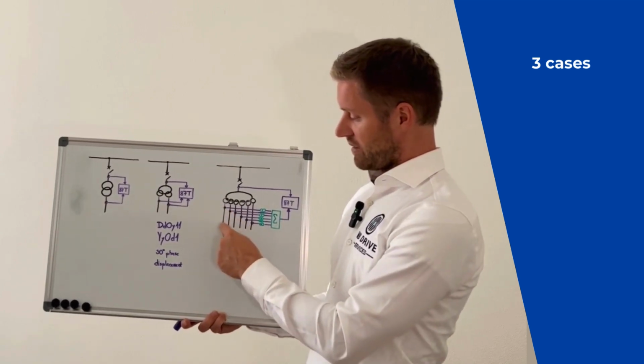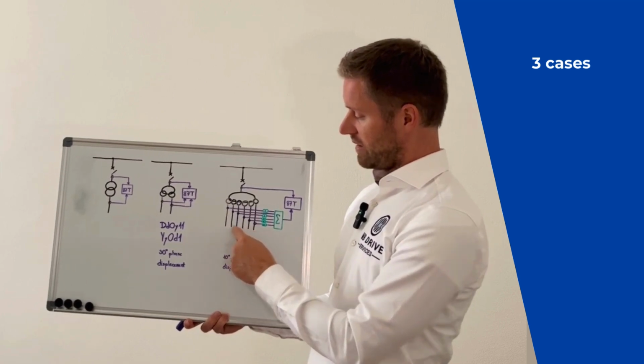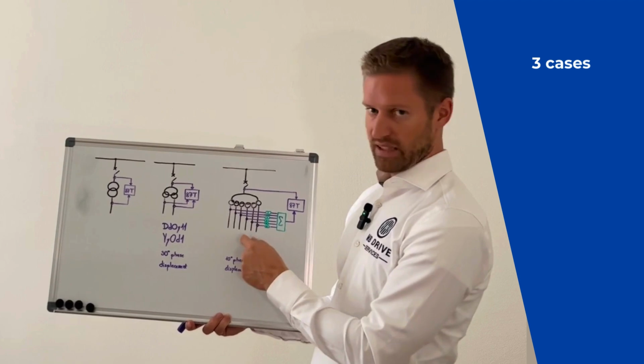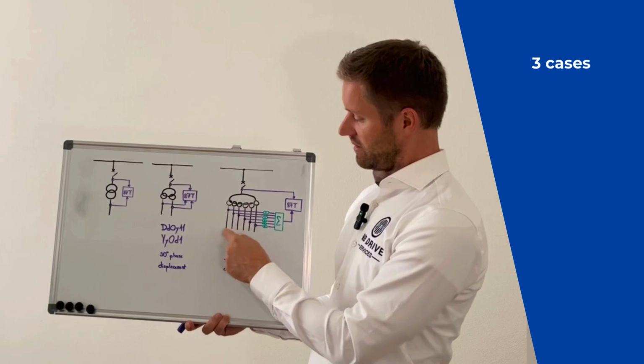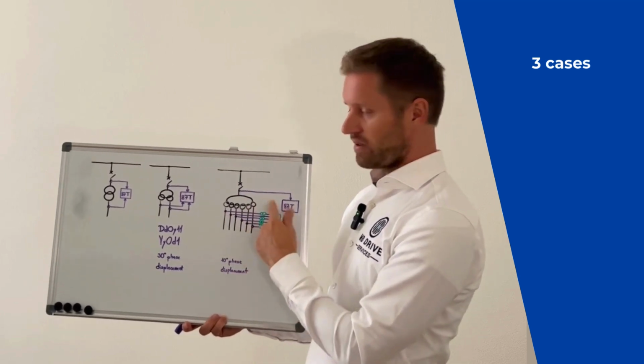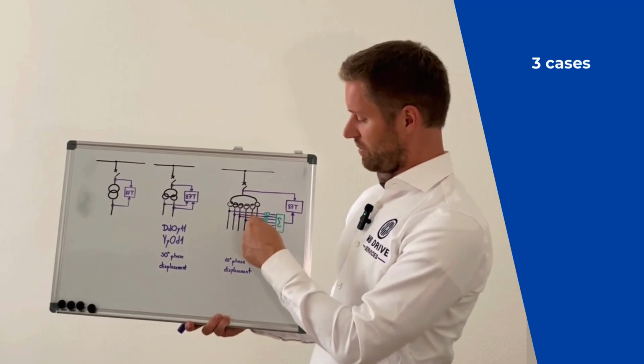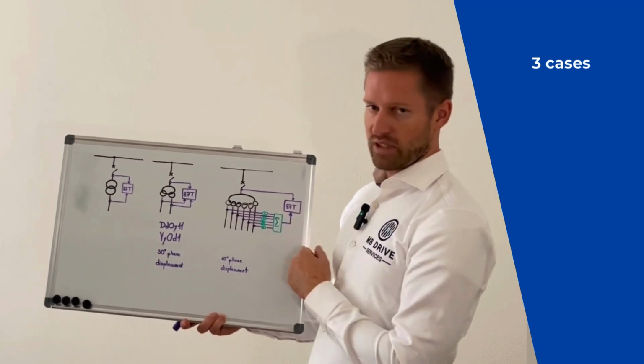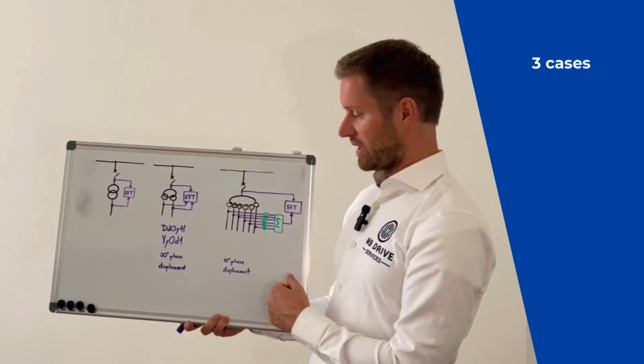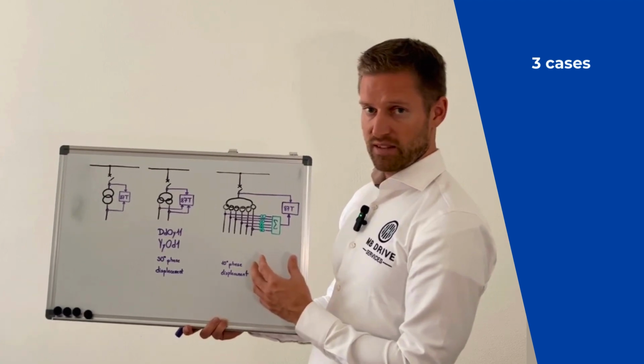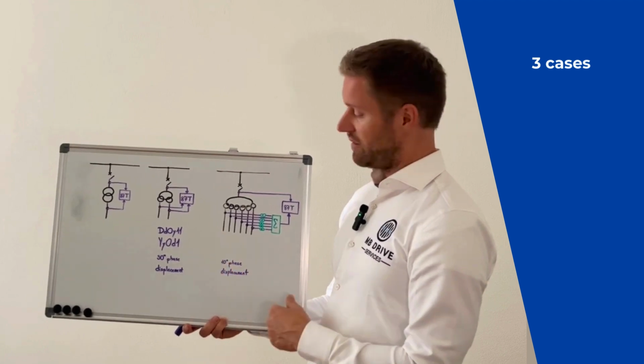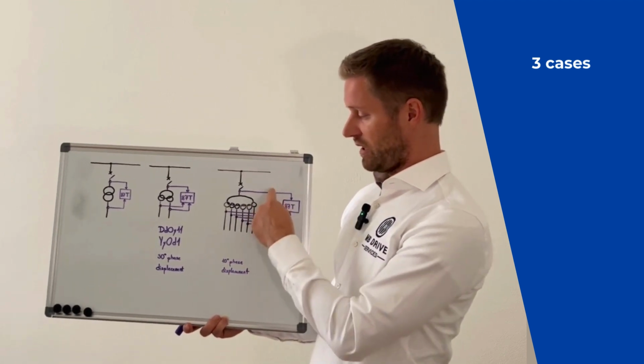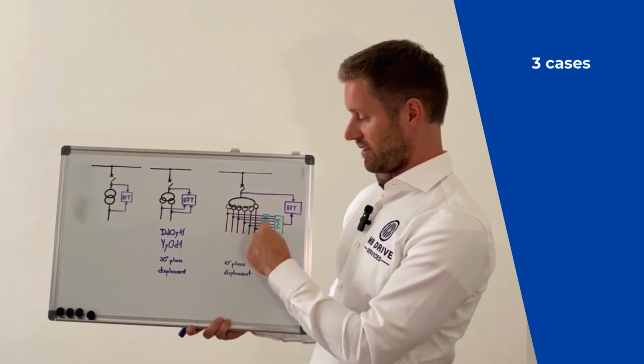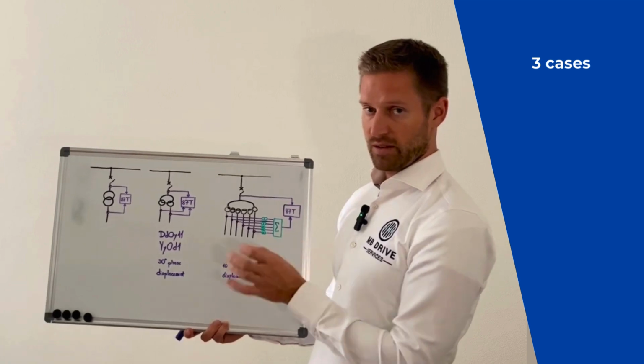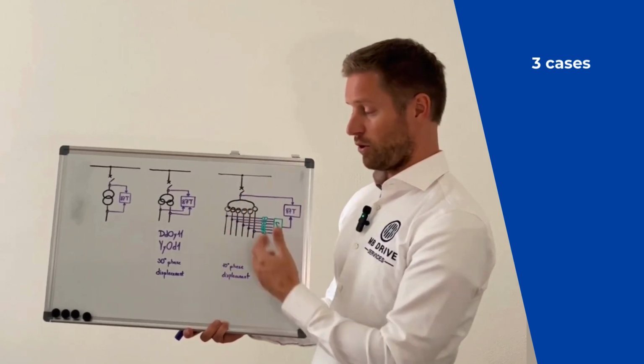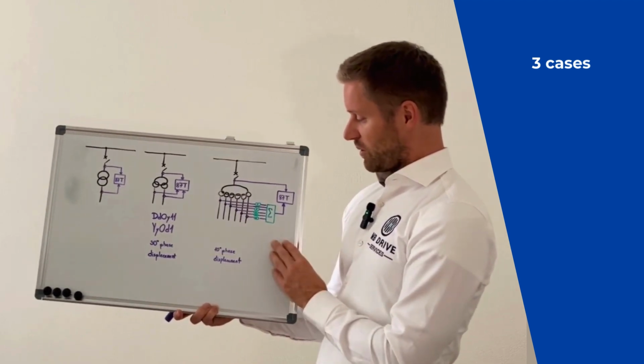And then as the windings are phase displaced, the currents flowing in each secondary winding are not in phase with each other, so we cannot just sum them up arithmetically. If you would just sum them up and feed the sum into the relay, then it would trip immediately. Because as I explained earlier, differential protection is appreciated mainly because of its sensitivity, and here we would have an error. The primary current would not be the same as this arithmetic sum of the secondary currents. So the relay would trip immediately, although there is no fault in the system. So this is of course not what we want.